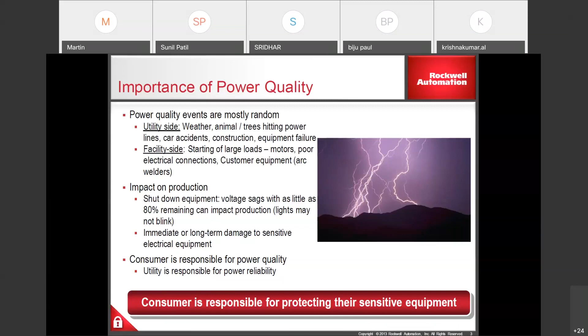Sometimes if it is very large equipment, it can even go beyond the transformers, even if a transformer is present. Then welding equipment and all those kinds of huge loads, when they are started, can cause these problems. Voltage sags with as little as 80% voltage remaining can impact production. The lights might not blink in that case, but if you look at the RPM of the motor or the control side of it, it can really experience a blink. This could lead to immediate or long-term damage to the equipment. The consumer is responsible for the quality of the power. The utility is responsible for the reliability. That's the takeaway of this slide.